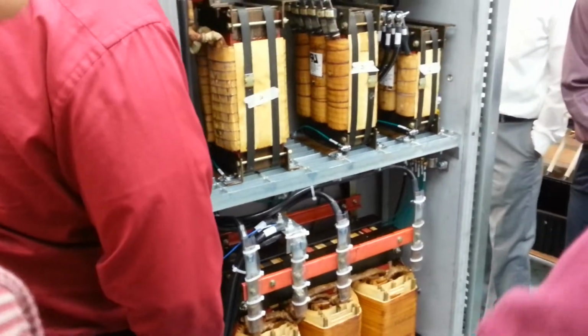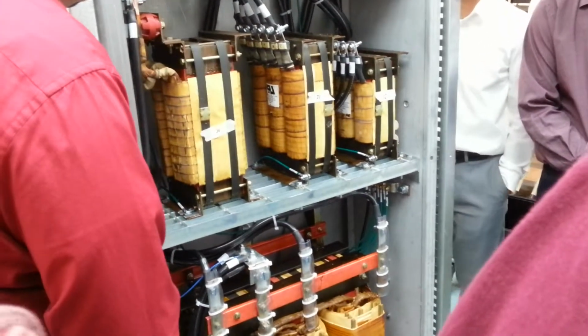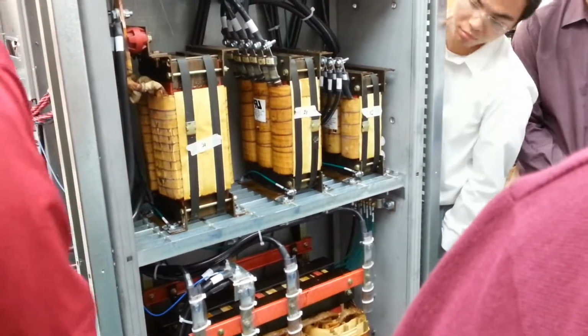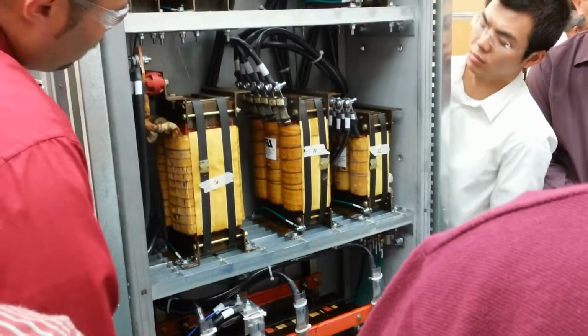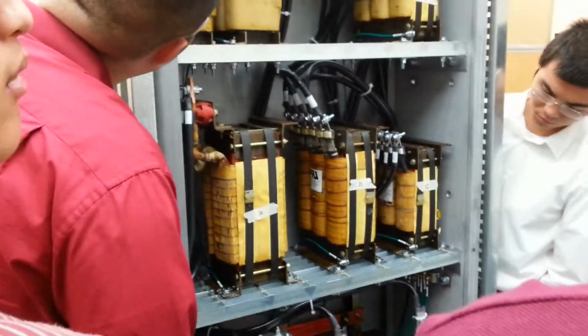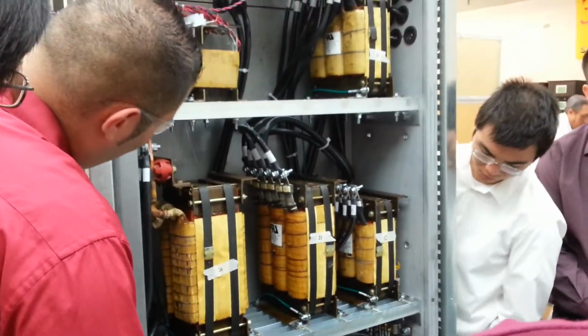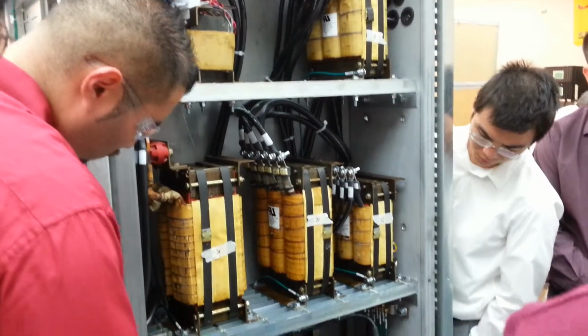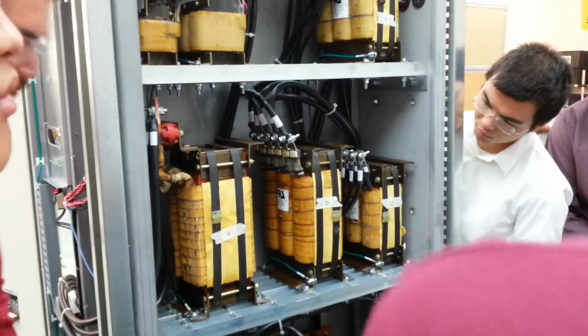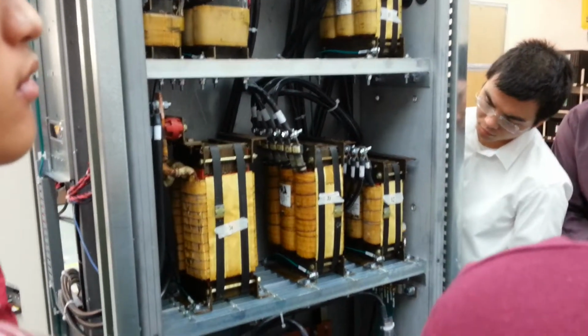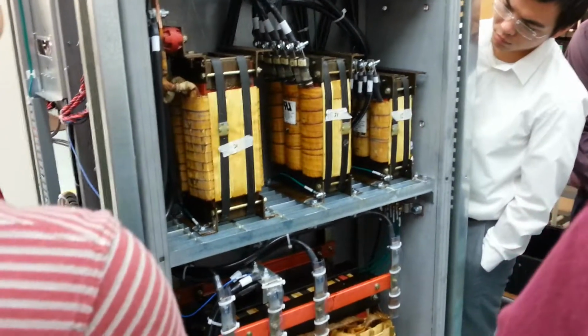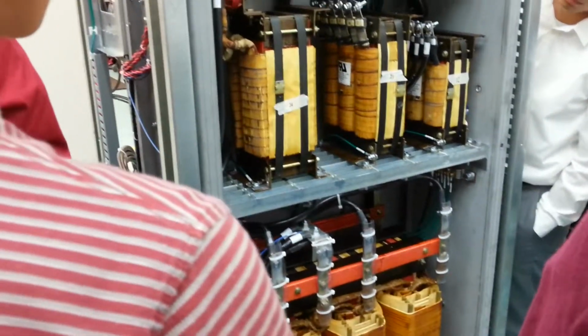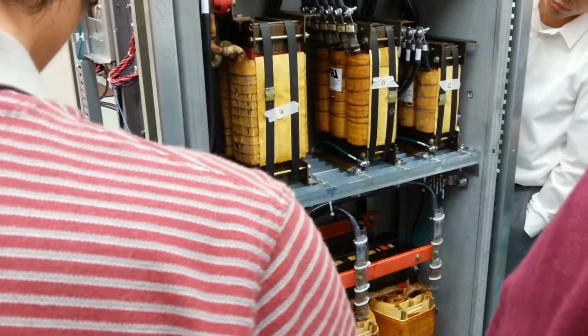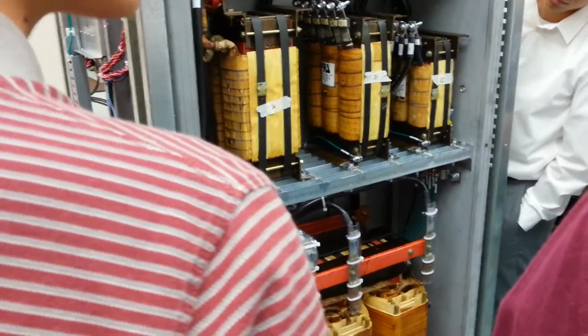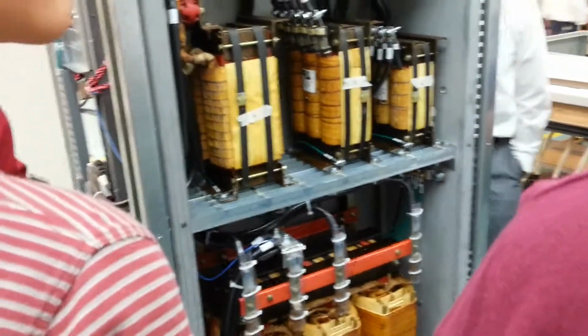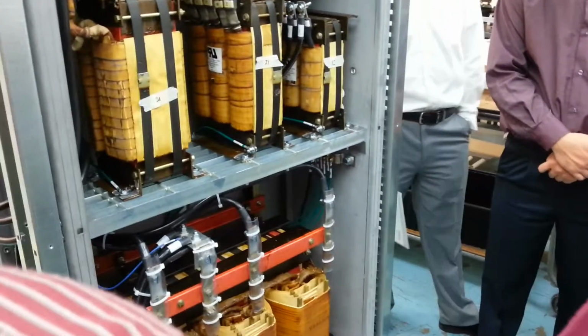The input side is an LC. Yeah, there's three of them actually. Each one is separately detuned for first, third, and fifth harmonic. So not one works hard. They all share the first, third, or fifth, or 500 or 300 hertz, whatever it is. They're all fine-tuned to take care of their own current. Because of course, when you start filtering that, you get current. So they're all tuned for a certain specific range.